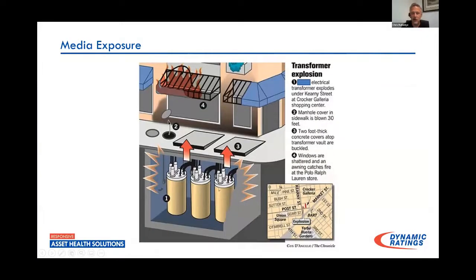So while these are not really network transformers, this is the best graphic I can show you, just some of the media exposure you would see. And like I said, every time we had one of these fail catastrophically, we were on the news that night, which is something no utility really wants to see. You don't need that negative publicity, but we can see in this event, this manhole cover was blown 30 feet away from where it was located.